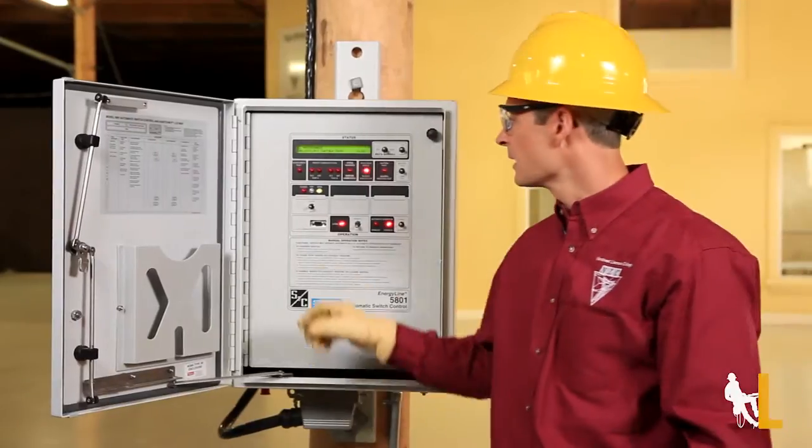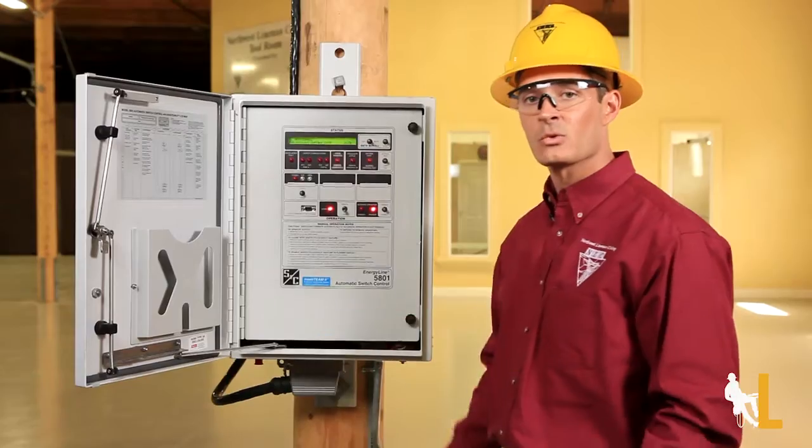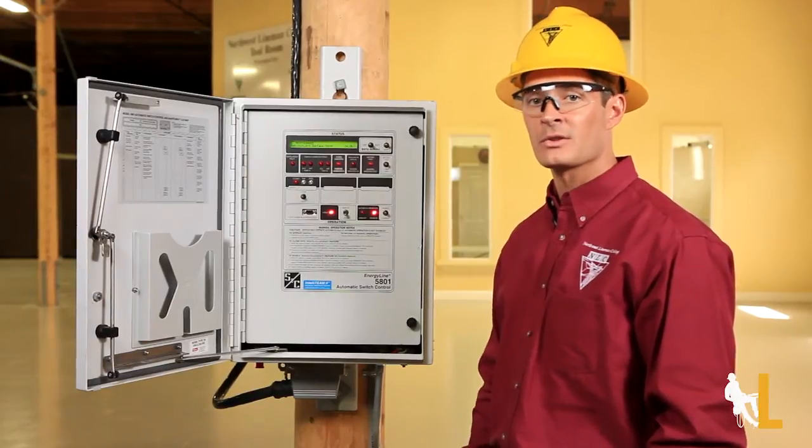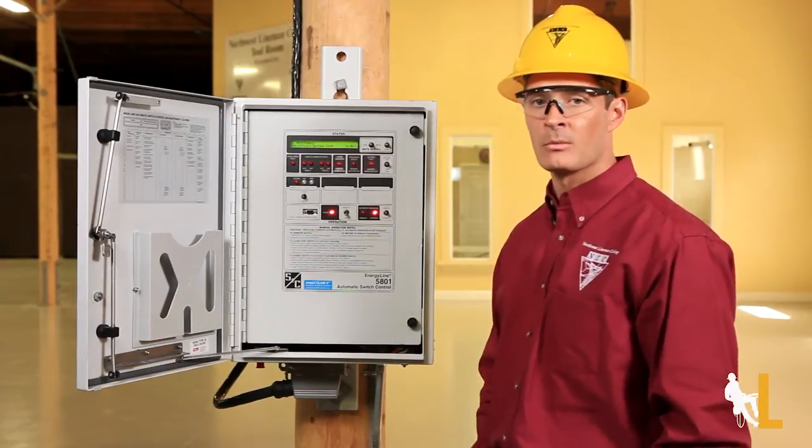If you open the panel and the trip light is on, that means that the switch is automatically open because of a problem on the line. Once the problem is clear, you can either close in the switch using the control panel or have SCADA do it remotely.